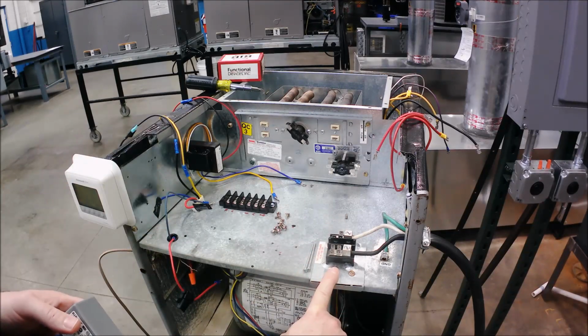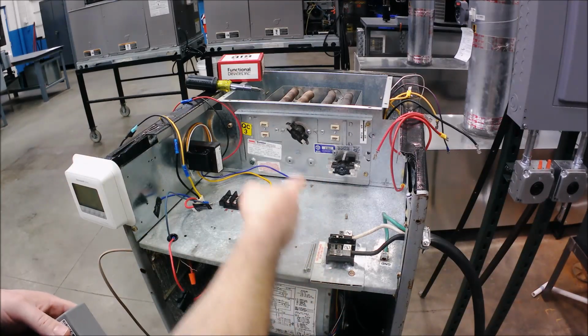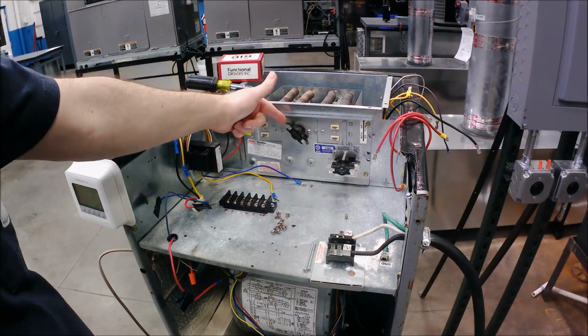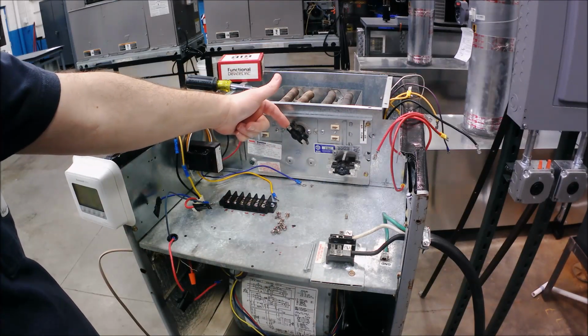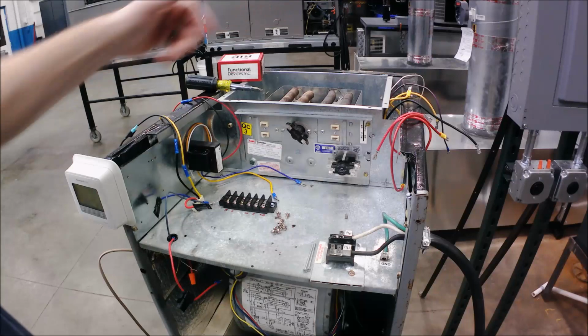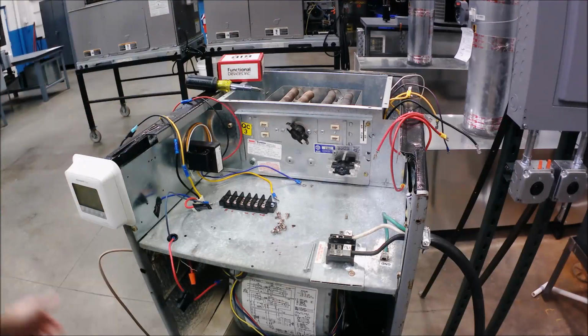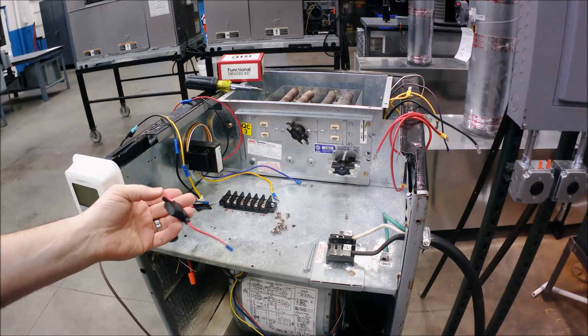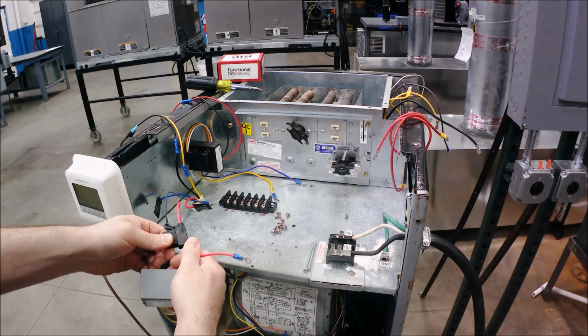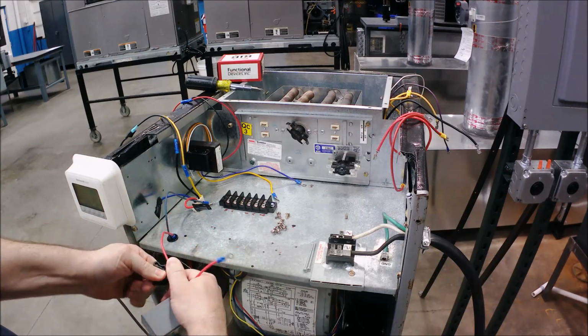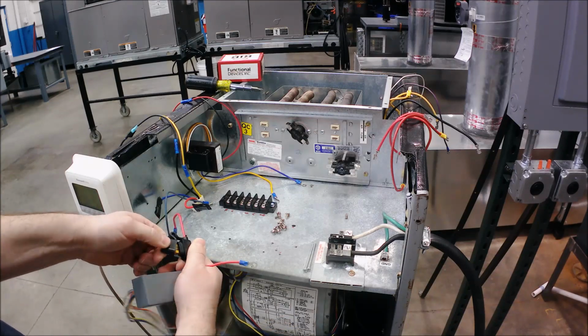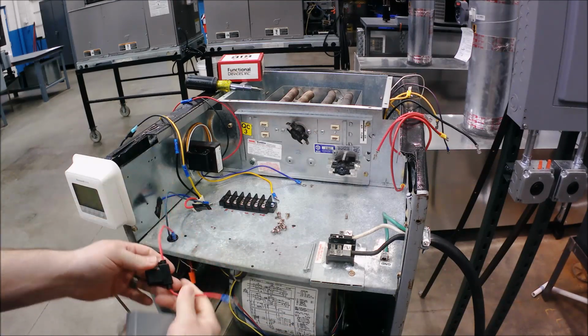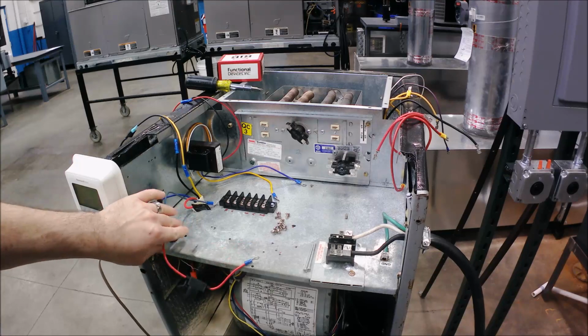So terminal block for high voltage over here. We've got sequencers. We have a double stack limit switch right here that is for our heater kit. We've got our transformer in the corner. I've mounted a thermostat right here on the side. And here is our fuse holder. I've also put a ring on the side of it. If you open it up, you'll see a 5 amp fuse right here. It's ready to go. So we're going to take it from scratch.